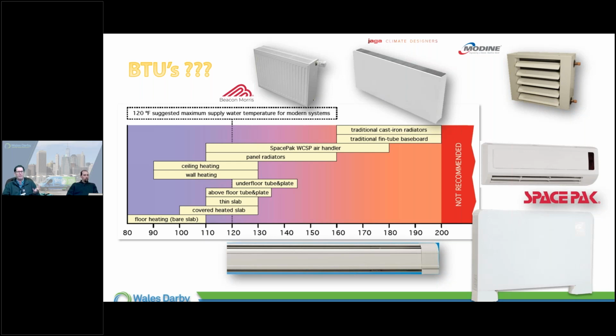You need to see the differences, because there are really low cooling loads, but there could be a really high heating load. So where do you size that machine? It can get grossly oversized, because when you switch from heating mode to cooling mode, you cause problems. So now you have to find this happy medium.